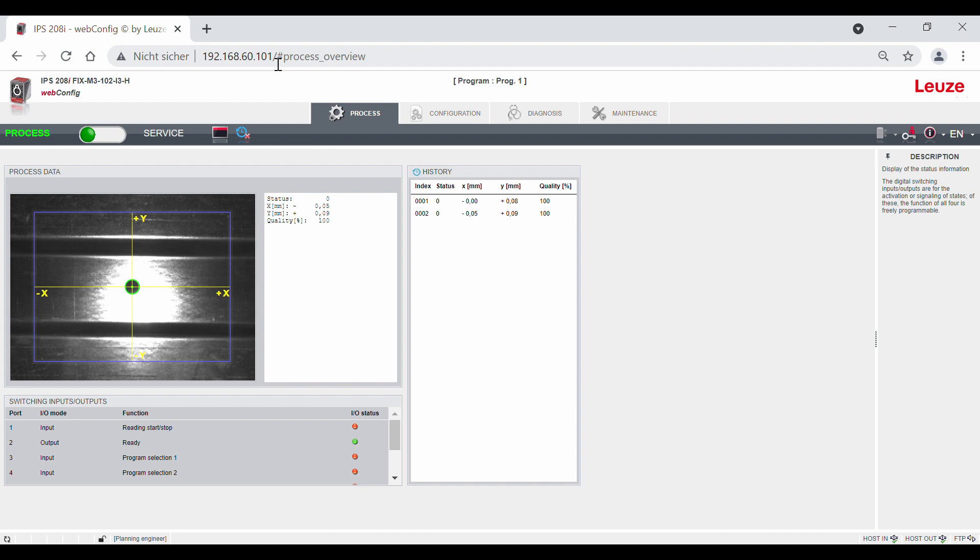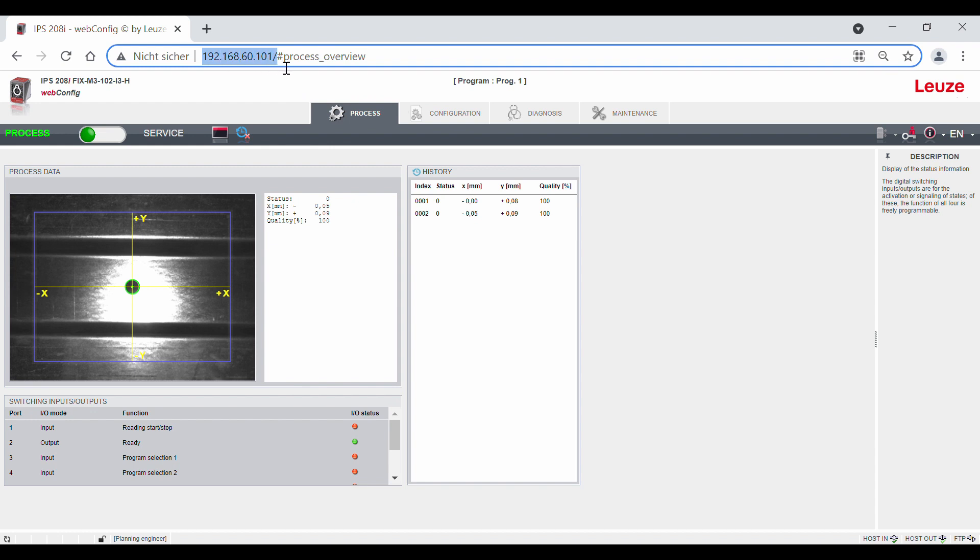When connecting, it is important that the IP address range of your PC is in the same address range as the sensor. By default, the sensor has the IP address 192.168.60.101 and is entered up here in the address line of your browser.